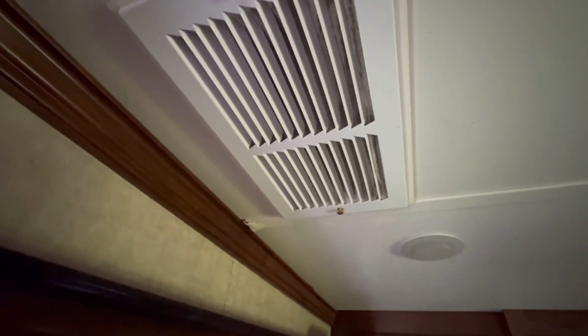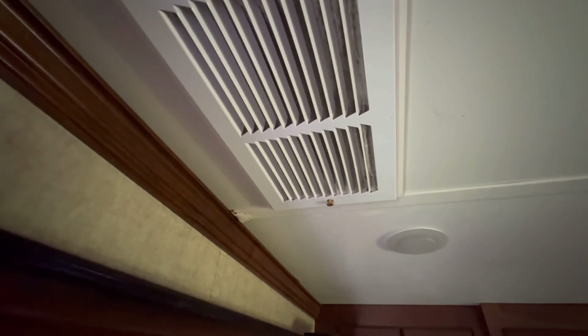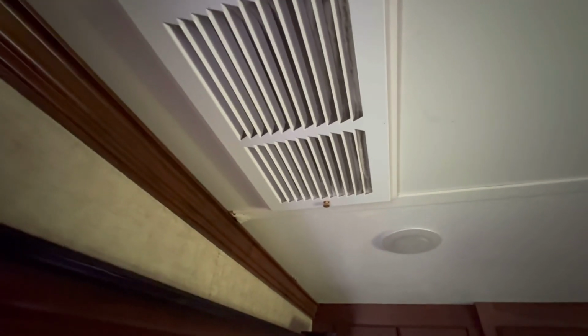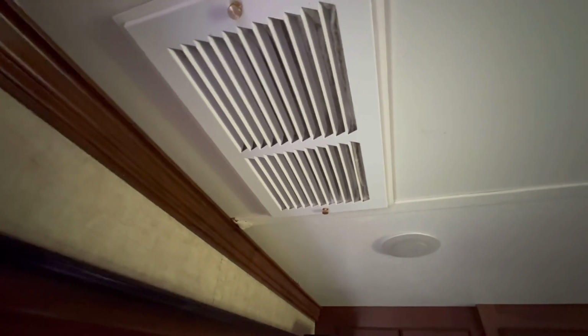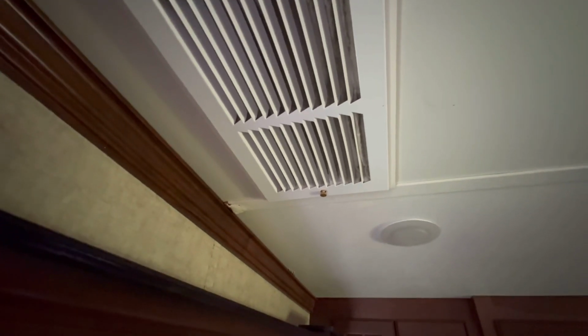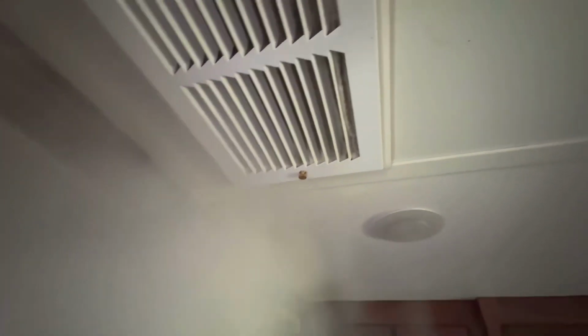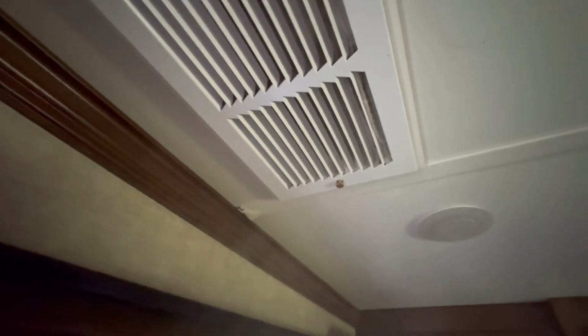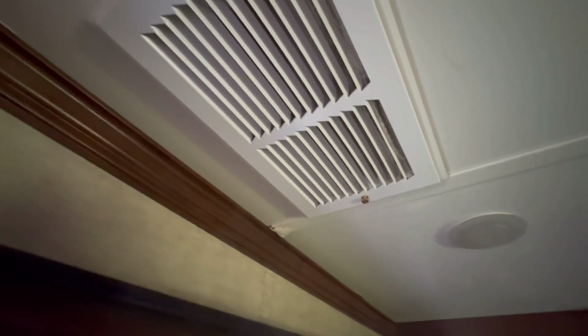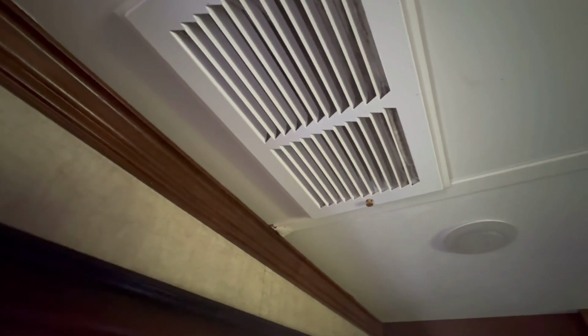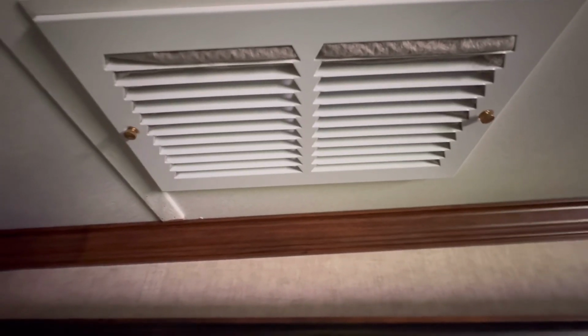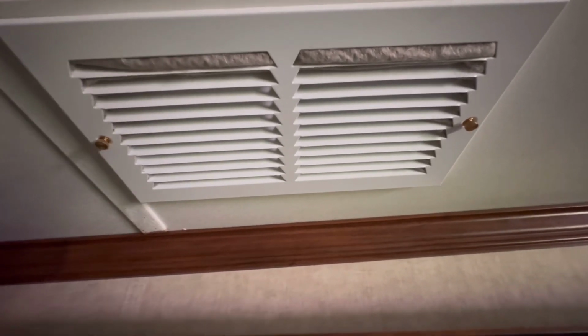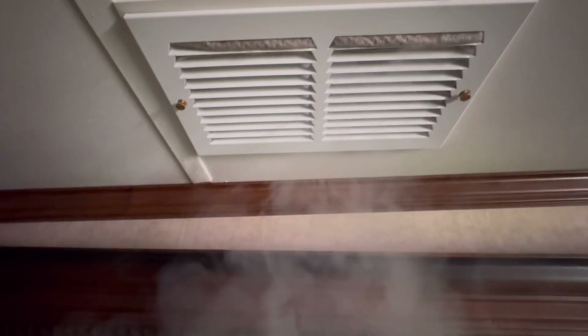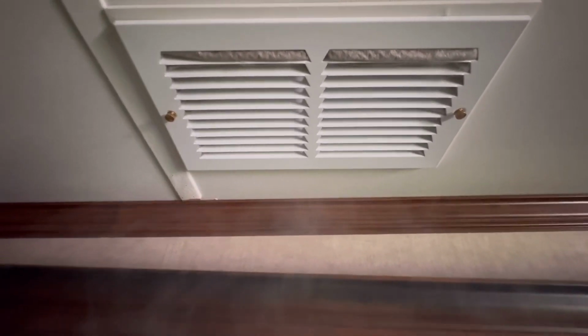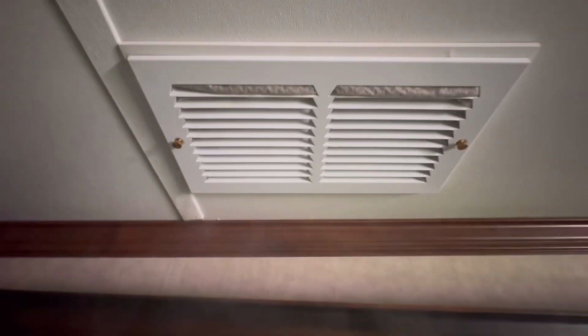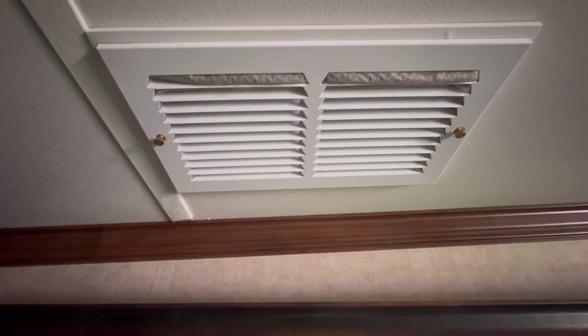Another test I like to do, and we'll just put a little liquid smoke up in the air and see if these return ducts draw that up and through there. We know that it will. And you can see that smoke dissipated rather rapidly right up inside the return duct. And we'll come over to the other return duct. There's the smoke. And you can see how quick it drew all that smoke up in there. That's what we expect to see.